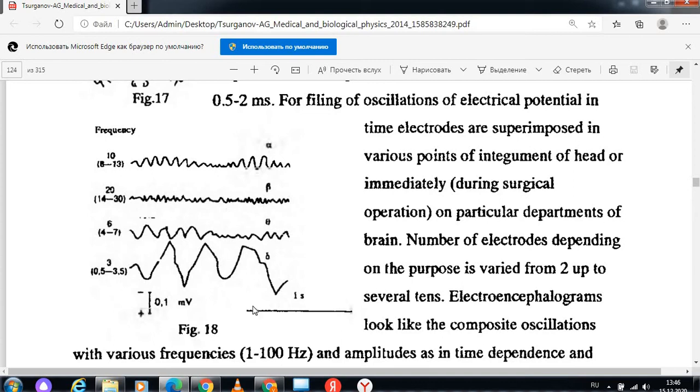electroencephalograms. So the reference of the distance on the graph is 1 second. Here it's a horizontal line, 1 second duration. And another type of calibration is the vertical line of 0.1 millivolt, from plus to minus. You can give a calibration of amplitude here in millivolts, the voltage difference between 2 points of the dipole.